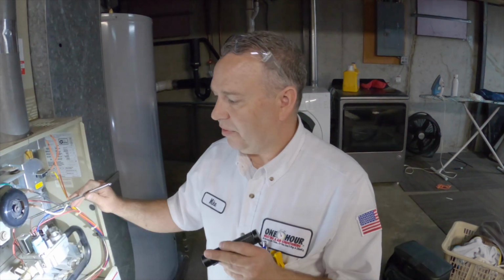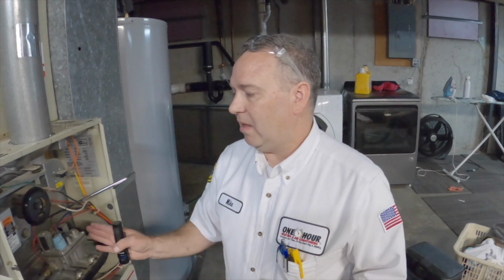The unique thing about this furnace is it's not like your typical heat exchanger cell, where all the cells are combined together. With this style, each one has a separate cell. So if a customer decides they just want to replace the heat exchanger, while they're in there they're not just going to want to replace the one that's cracked — they'll want to replace all of them, which in the long run costs more money.